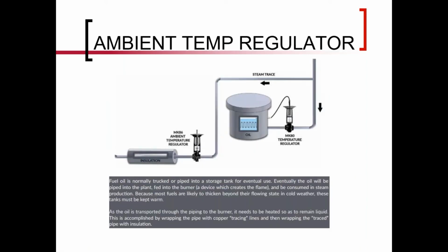Very, very straightforward. And then kind of a neat application where it uses both. So you've got a temperature regulator with the bulb actually in the oil, probably a thermowell, so you don't have to drain the tank if you need to change anything, but you've got steam coming in there to keep that oil heated, and then also to an ambient temperature line, so that there's probably, again, water in here, or whatever it is you need to keep at a certain temperature, and that will open and do so based on the temperature outside.